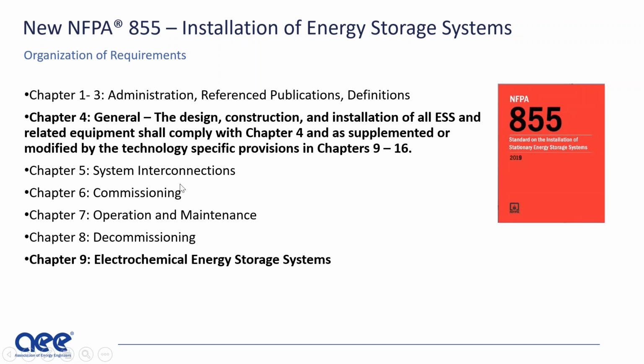It also talks about system interconnections, commissioning, operation and maintenance, and decommissioning. One issue with batteries is decommissioning—what do you do once your batteries are done? Then there's operation and maintenance, which is really important. Some energy storage systems you set in place and turn on, but you still need to maintain the disconnects and make sure connections don't loosen with heating and cooling over time if they're outside. You also need to deal with proper maintenance if you're using something with more mechanical operation.